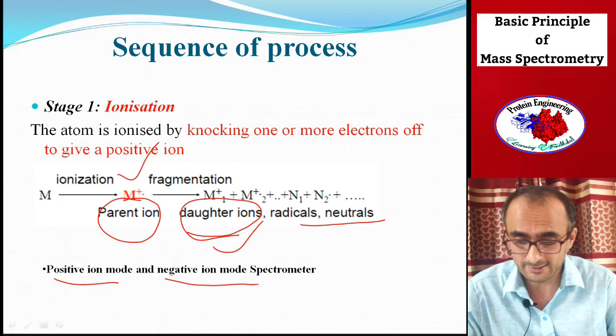So in the ionization chamber, you have an electrically heated metal coil which is heated and radiates electrons. Now these electrons are collected by an electron trap that is positively charged, and they have very high speed also. When you introduce your sample in vapor state, your analyte enters the ionization chamber, and in between, these electrons are bombarded on that analyte. As a result, these electrons are able to knock off an electron from the analyte, and the analyte becomes positively charged.